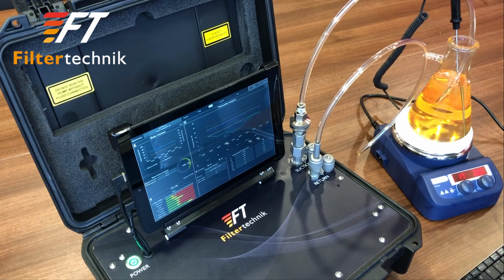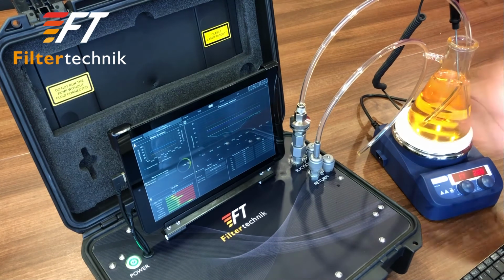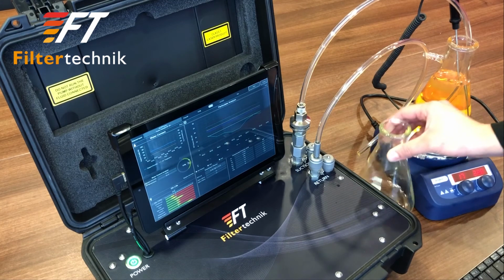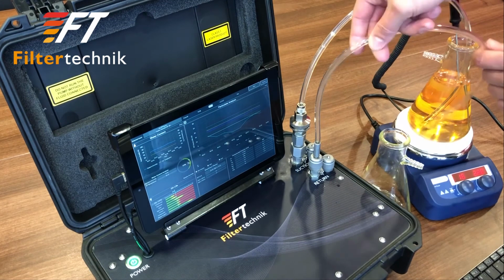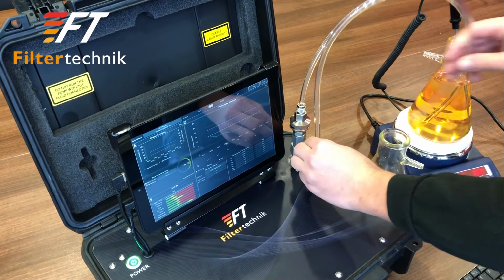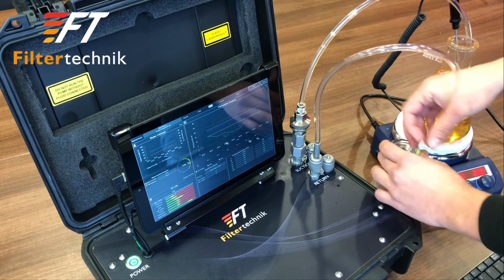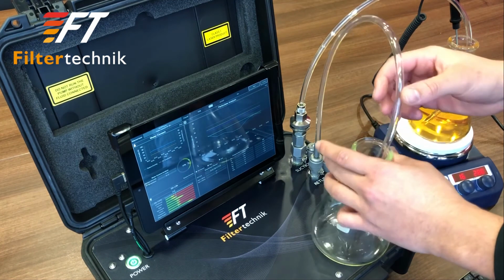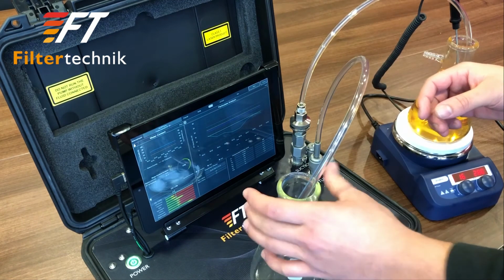We're going to place the suction line into the new oil, ready for the purging. Using an empty flask, we're going to get the return line and purge the oil that was previously used in the unit so there's no cross-contamination.